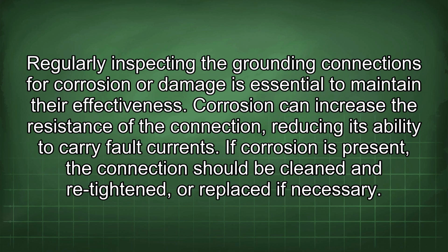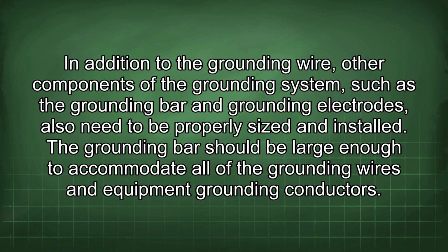Regularly inspecting the grounding connections for corrosion or damage is essential to maintain their effectiveness. Corrosion can increase the resistance of the connection, reducing its ability to carry fault currents. If corrosion is present, the connection should be cleaned and retightened or replaced if necessary. In addition to the grounding wire, other components of the grounding system, such as the grounding bar and grounding electrodes, also need to be properly sized and installed.